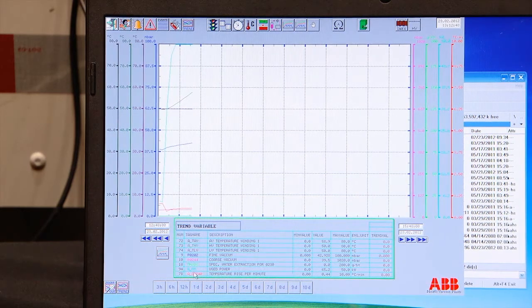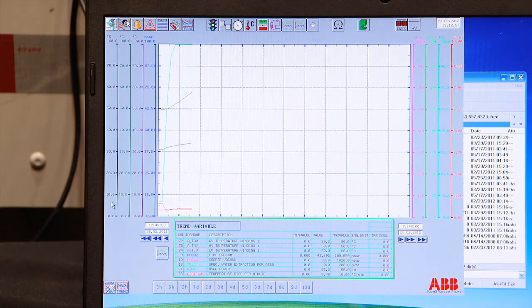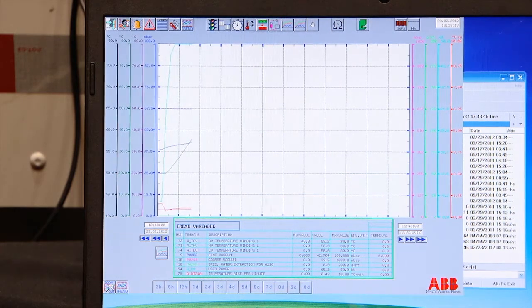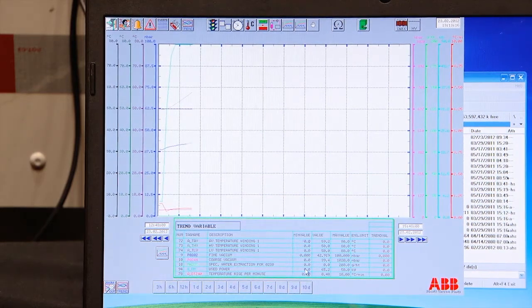These are color coded. You have the minimum value, you have the maximum value for the scaling. These are the same values as you see here on the side. So if you want to change the scaling, for example, average temperature, you don't want to start at 0, you want to start scaling from 40 degrees. Just click on the minimum, change it. The scaling here changes, and you see a little bit different resolution on the screen. Very convenient is to have the same scaling for all temperatures. Otherwise you will get a little bit confused.